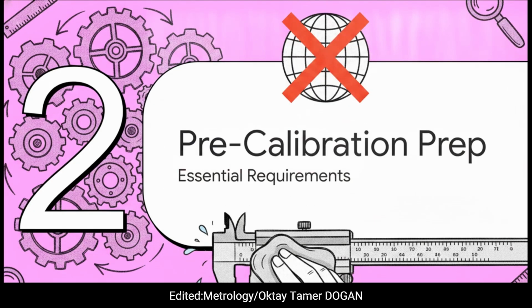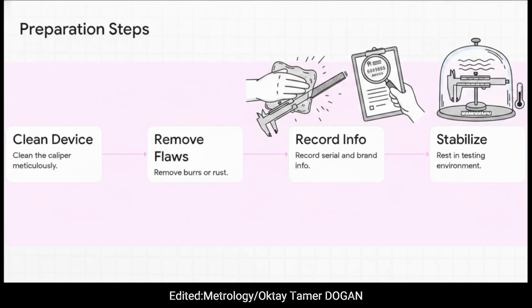Moving on to Section 2, essential pre-calibration requirements. Because, let's be real, even the most rigorous global standards are absolutely useless if your physical prep is flawed. Imagine looking over the shoulder of a master technician. Before they even touch a precision block, they run through the strict prep phase. First, the caliper gets meticulously cleaned. Second, any burrs or rust are completely removed. Why is that so crucial? Because even a microscopic metal burr acts like a tiny wedge, throwing off a micrometer reading and instantly invalidating your test. Third, we record all the identifying info, brand, serial numbers, scale divisions for total traceability on the final cert.